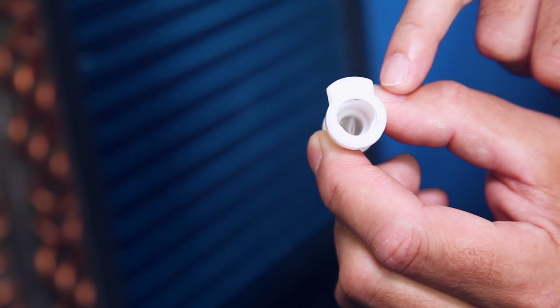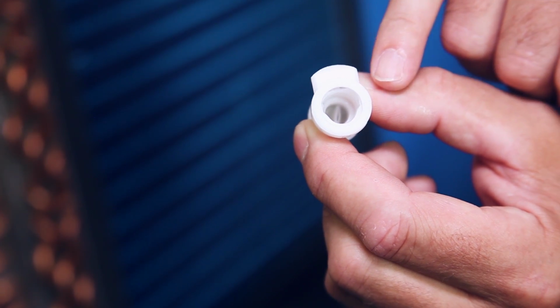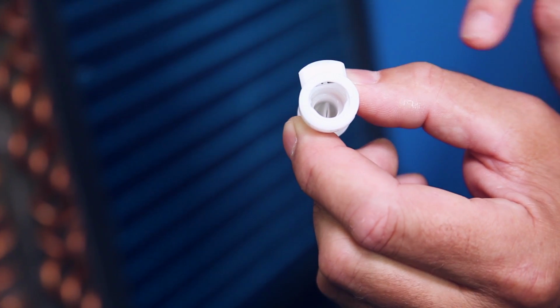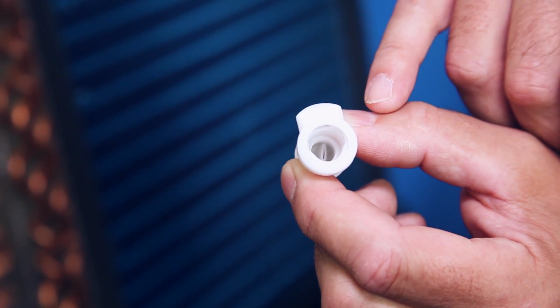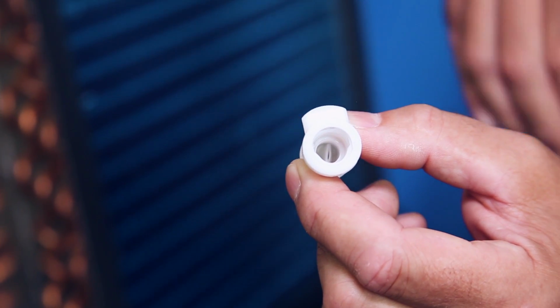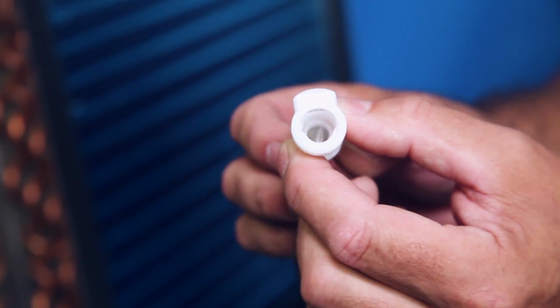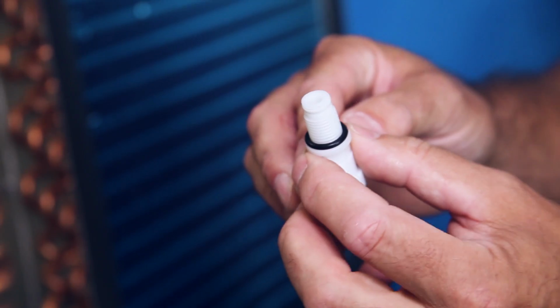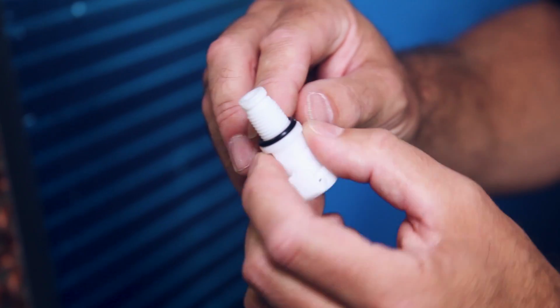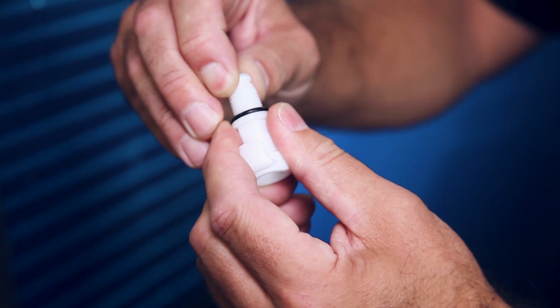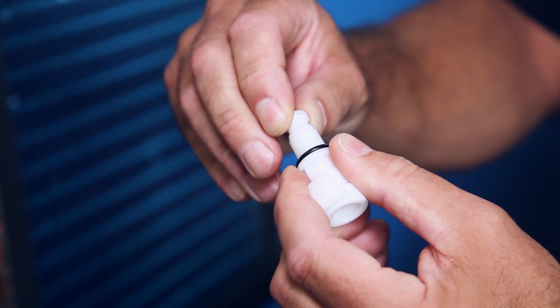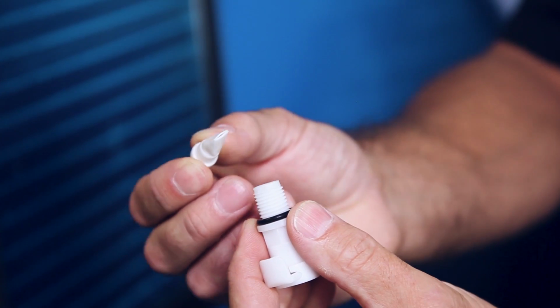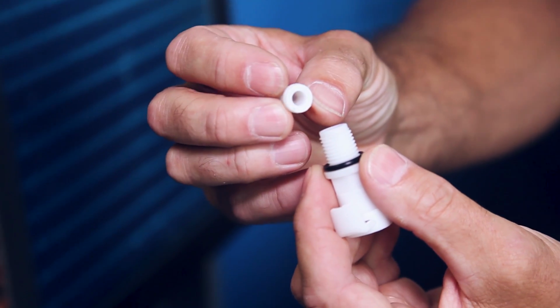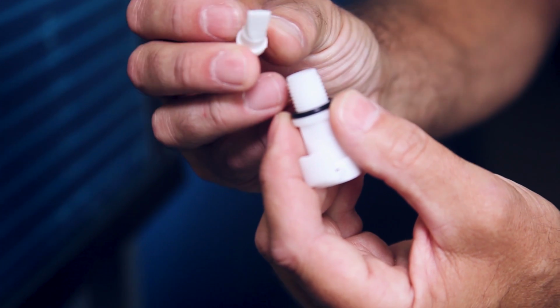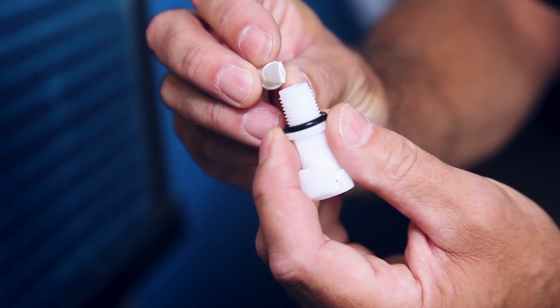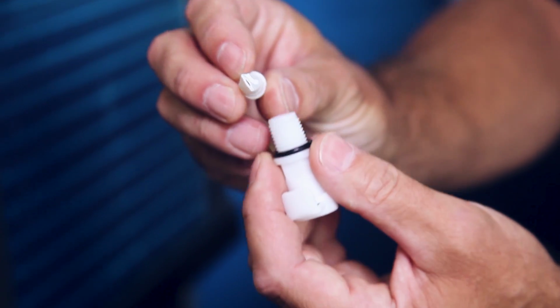Looking through at the duckbill check valve, you'll notice it may have a slight separation. A separation of 1/16 of an inch or less is acceptable. It relies on the water pressure from the output line to push back and close the valve. On the inlet side of the check valve, inspect the O-ring, replace if damaged, and you may remove the duckbill check valve from the fitting and inspect the inlet side and the outlet. Again, replace if the gap is greater than 1/16 of an inch or if there are any tears.